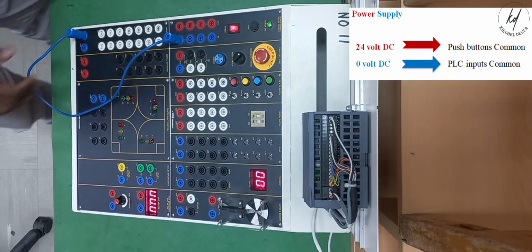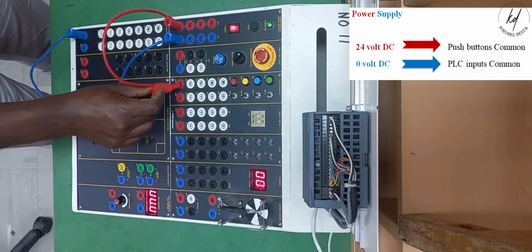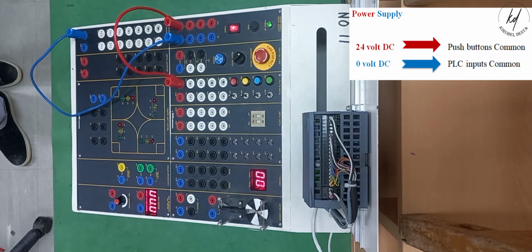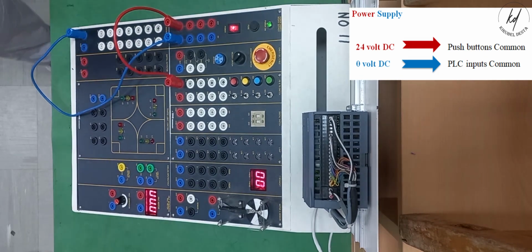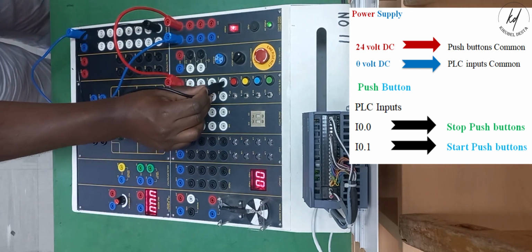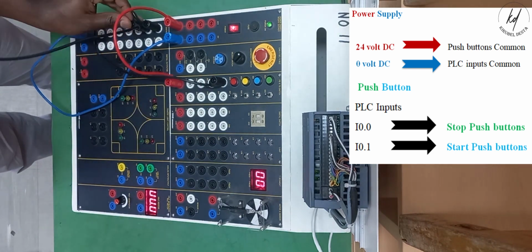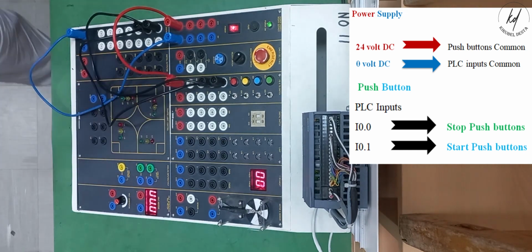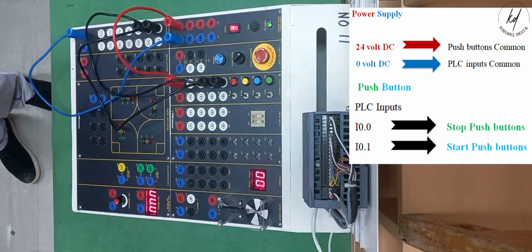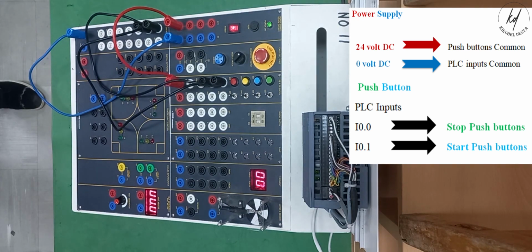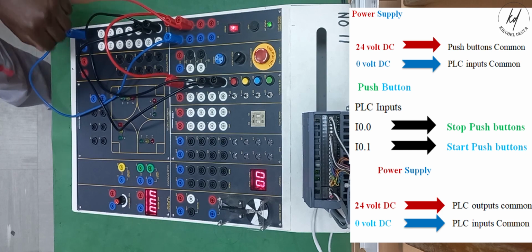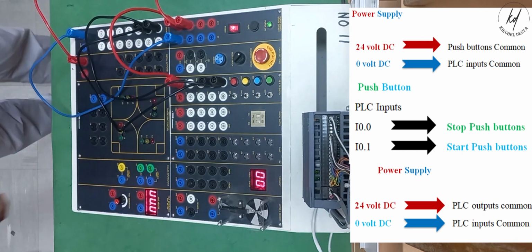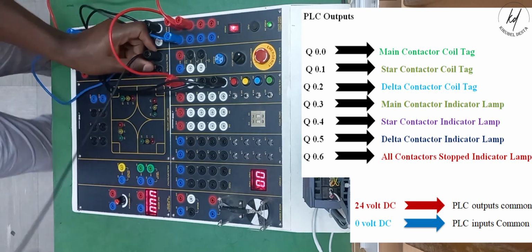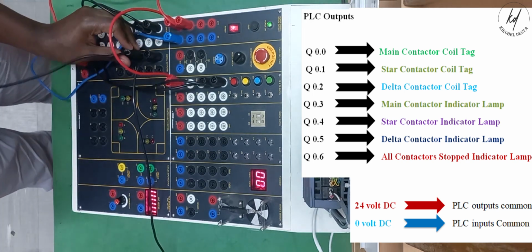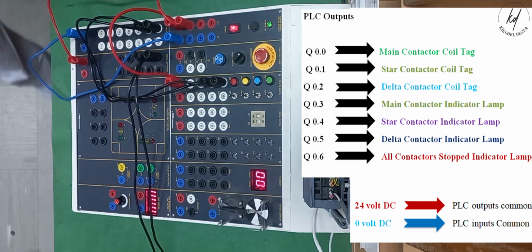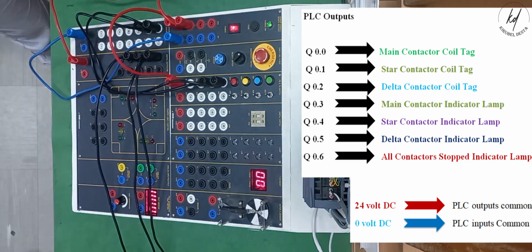Let's get into PLC wiring. To do that, provide 0 volt to the PLC input pins and 24 volt to the push buttons. Then connect the PLC inputs to the push buttons' respective addresses. Then connect the 24 volt power supply to the PLC common output address, then to the main, star and delta contactor coil tags respectively. At last, their respective indicator lamps need to be connected to indicate their status, and in addition the stop status is also indicated through its indicator lamp.